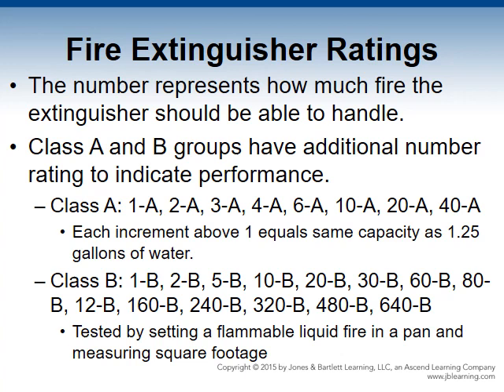Class B extinguishers are tested by setting a flammable liquid fire in a pan; the rating is determined based on the pan size and is proportionate to its square footage. A 120B extinguisher means it should be able to extinguish a 120 square foot pan fire. As the fire becomes larger, a greater amount of agent is needed and the relationship is not as proportional. Ratings include 1B through 640B. Class 1B through 20B are based on indoor fire tests, and Class 30B and above on outdoor fire tests.